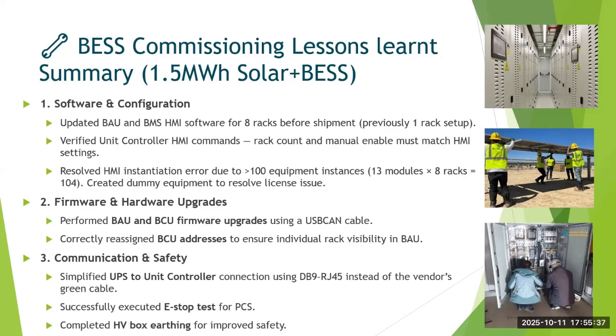And an emergency stop was there to operate the PCS. So we tested those emergency stops during operation. If I press each emergency stop, does the BESS with all the racks open its contactors, and does the PCS not get DC power, so that it opens the AC and DC contactors of the PCS? We checked all those things, and also earthing has to be proper, so we measured the earthing as well.